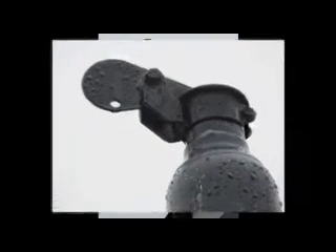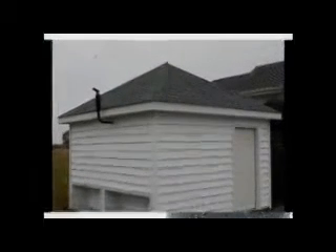The engine exhaust must be run outside, and a good muffler is a necessity. I have both a muffler and a glass pack, along with a gravity rain vent at the end of the tailpipe — you don't want water in the exhaust pipe. Make certain that it runs above the fascia of your soffit. The maximum temperatures I see are under 300 degrees Fahrenheit anywhere along the exhaust line. I use fiberglass cloth wrap and fiberglass rope where the exhaust pipe penetrates wall sections.